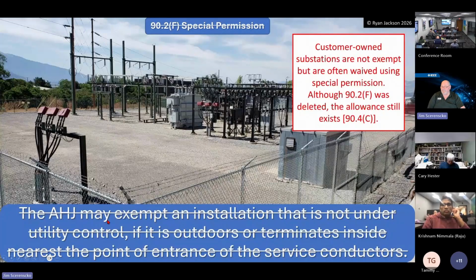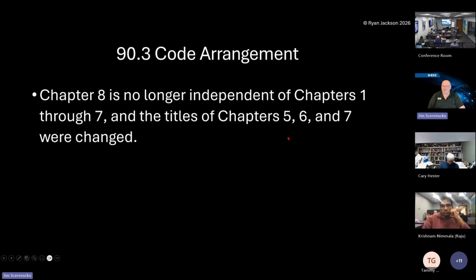The authority having jurisdiction, the AHJ, may exempt an installation that is not under utility control if it is outdoors or terminates inside the nearest point of entry of the service conductors. Again, the little thing here: customer-owned substations are not exempt, but are often waived using special permission. Although 90.2(F) was deleted, the allowances still exist in 90.4(C). So the authority having jurisdiction can exempt certain things.